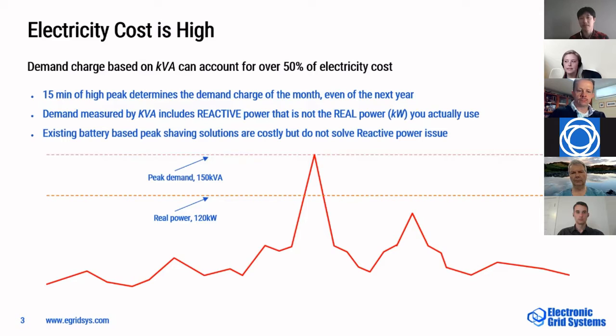In addition, the power demand is measured based on kVA. You don't have to know exactly what kVA is, but remember it includes both real power that does the work and reactive power that just runs a high current through your meter and does nothing. For example, if the peak demand is 150 kVA but the real power is only 120 kilowatts, you actually pay 25% more, and that doesn't make sense.